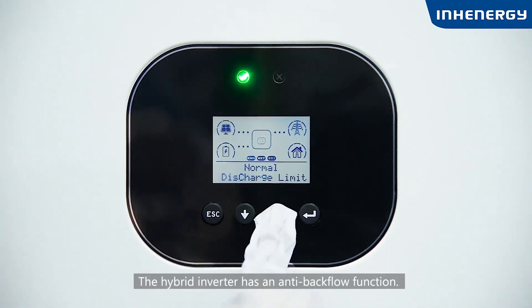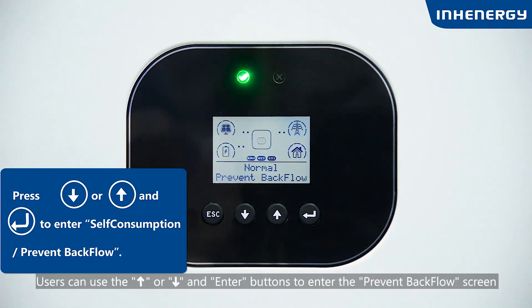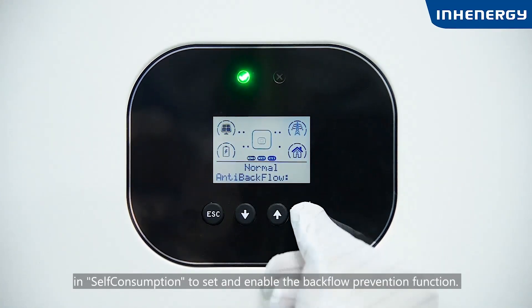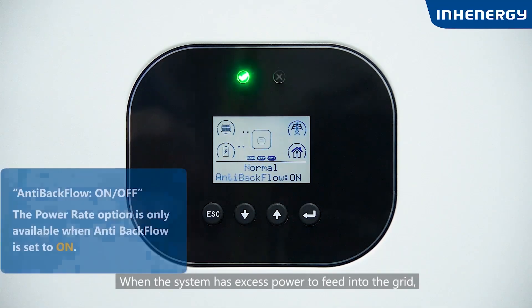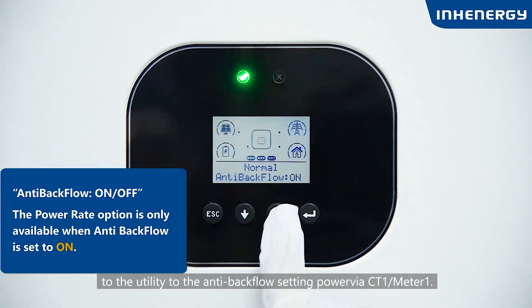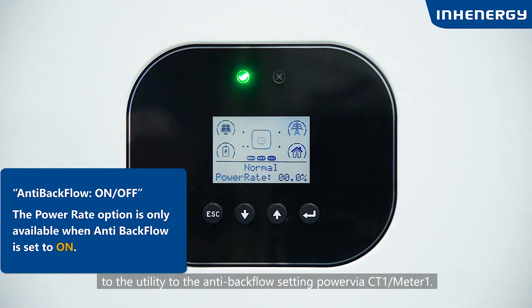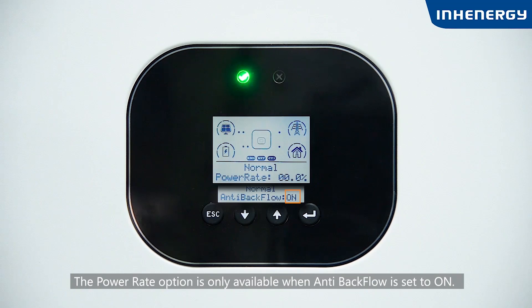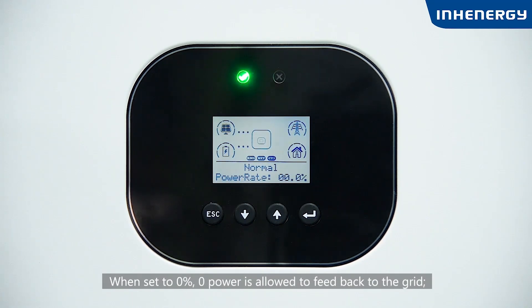The hybrid inverter has an anti-backflow function. Users can press the up or down and enter buttons to access the Prevent Backflow screen in self-consumption to set and enable the backflow prevention function. When the system has power feeding into the grid, the hybrid inverter limits the output to the utility to the anti-backflow setting power. The Power Rate option is only available when anti-backflow is set to ON. When set to 0%, no power is allowed to feed back to the grid. When set to 50%, 50% of the inverter's rated power is allowed to feed to the grid.